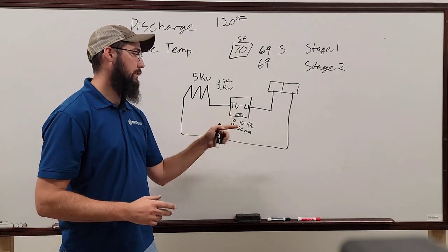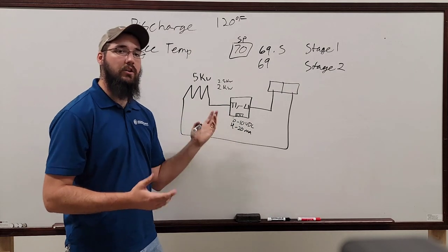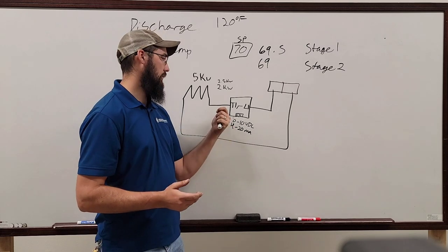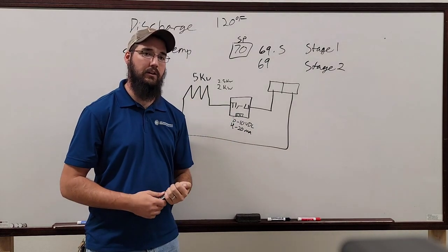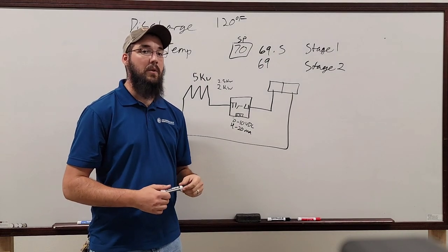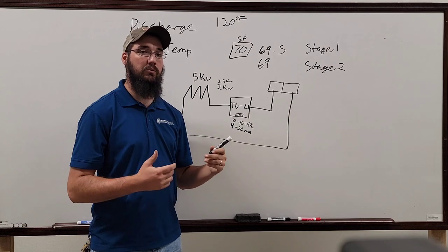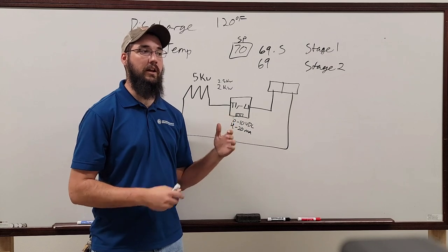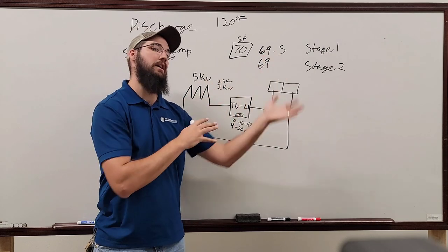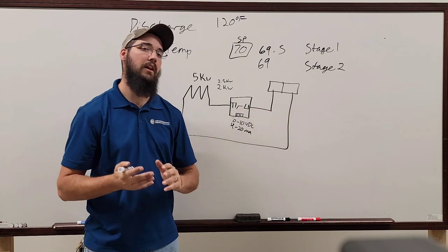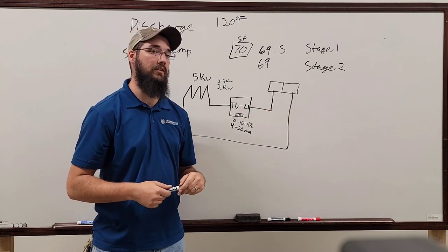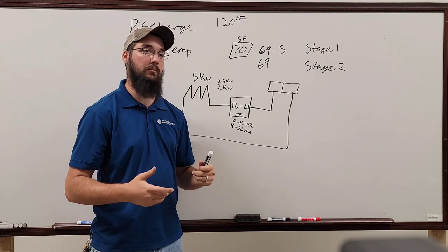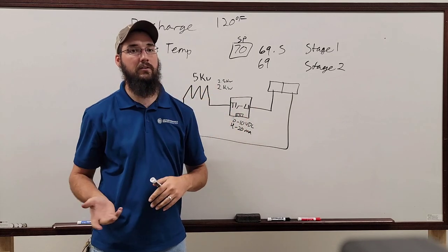Anyway, so you would put your meter in line, and then you would see, if you're calling for, say, 10 volts DC, and the heater's barely putting out any heat, something's going on. Most of the time, these either work or fail. In my experience, it's pretty rare to see one intermittently not really putting out voltage. I don't think I've ever run into that scenario. I'm not saying it's not possible, but I've never seen that. When I walk up to them, they're either functioning or they're not.